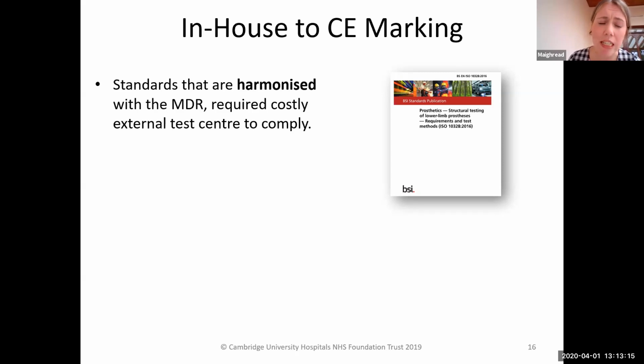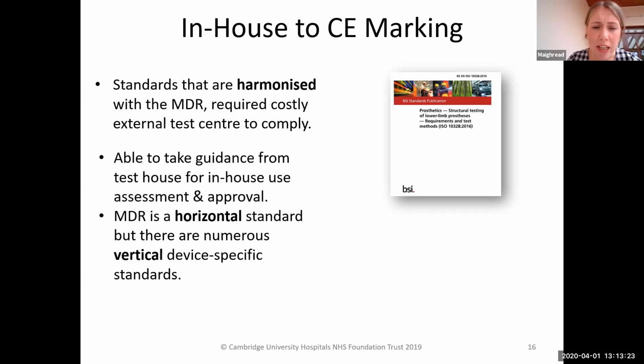So we reached out to these test centers and got some quotes for what testing would be required for our device and the cost of this. And we then assessed the cost, and we decided that the cost benefit of CE marking the device wasn't in favor of putting a CE mark on it. So we then decided to go under the in-house option for the device.